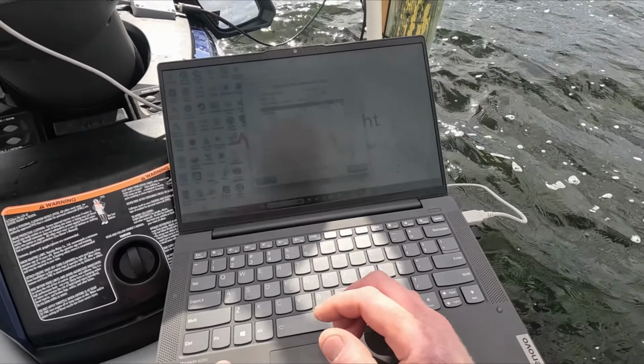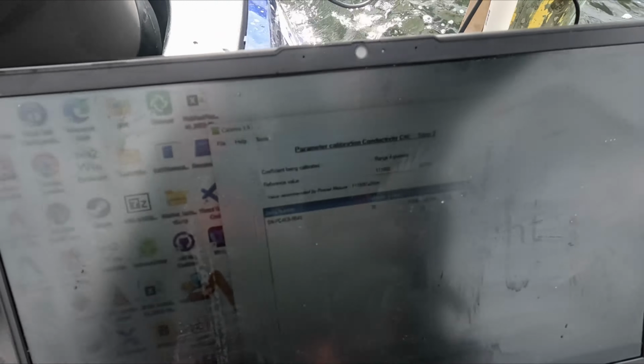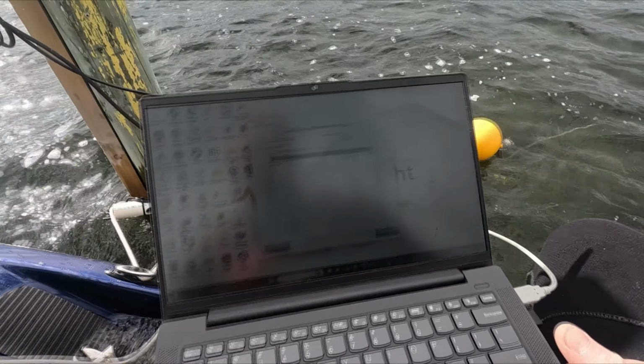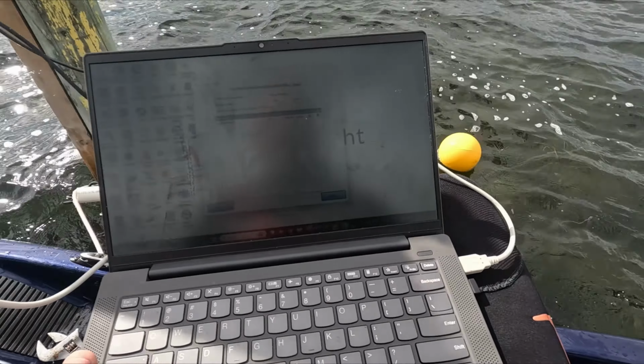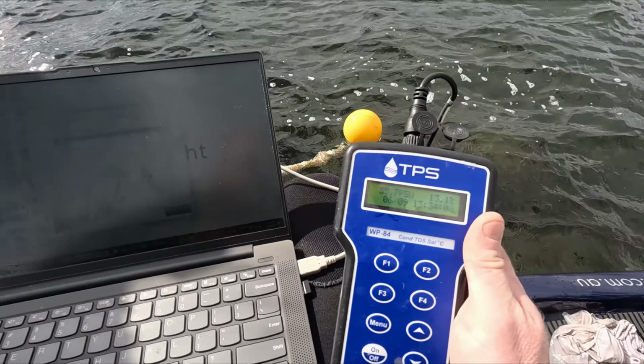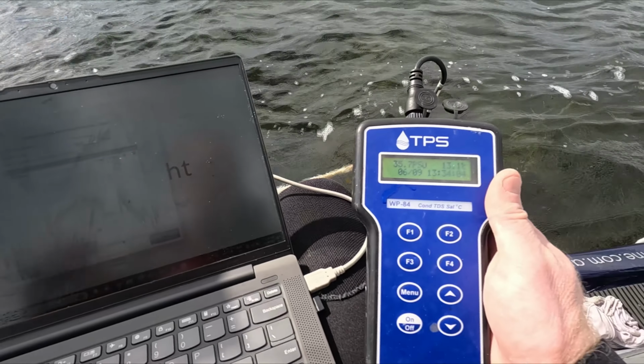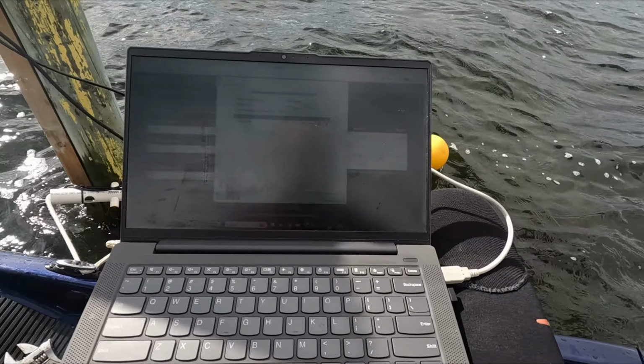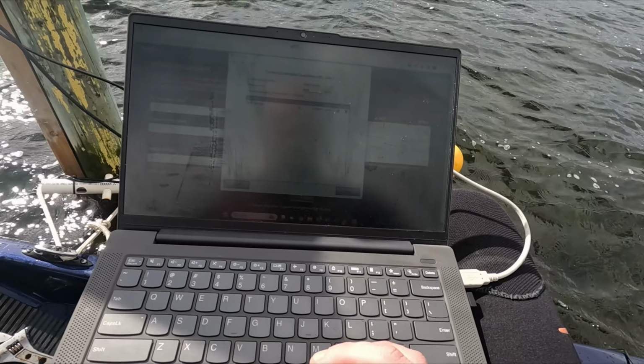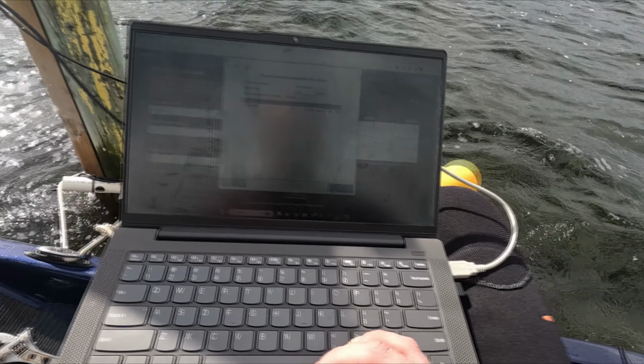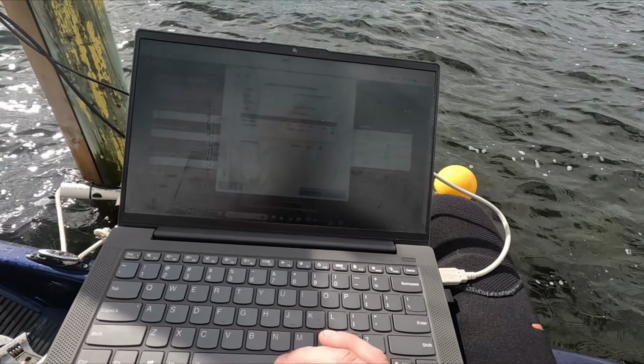Okay, looks like we've got our zero measurement, so we can hit next on that. Now we need to get our in-water measurement, so we will deploy the sensor back into the water and we'll wait for the measurement to settle, and we're looking to compare that with our handheld, which at the minute is 35.7 PSUs at 13.1 degrees. So once we've got the value from our calibrated instrument, we can input that here, wait for this measurement to settle, and it looks like we're about there. So we can send that calibration off to the sensor, validate, and that sensor is now calibrated.